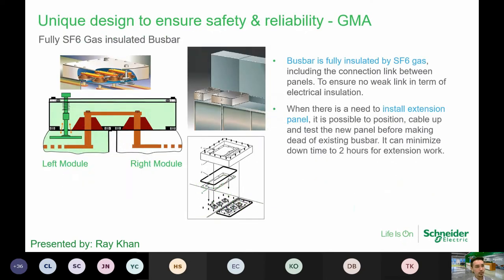Now, one of the very common interesting questions is when we do a panel expansion. This is how it's usually done. There'll be a box at the top, and the box eventually will be filled with the SF6 gas. We call it the busbar coupling tank. The one in the center of this picture gives us a clearer picture of where it joins the adjacent panels to the main panel. You will see that the main busbar and the busbar connection link between the panels are housed inside this pressurized SF6 gas. This feature provides users good service continuity.